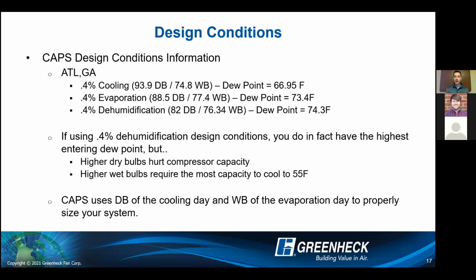So if you go into CAPS or you're working with Holden and they're in CAPS, the design conditions and the weather bin data that we're pulling out to standardize your selections are that dry bulb of the cooling and the wet bulb of the evaporation to make sure that we're hitting on, okay, this higher dry bulb is going to hurt compressor capacity, but we need to know about the higher wet bulb because that's going to require more capacity. Versus the dehumidification, while it does have the highest dew point, it might actually give you less capacity than you actually need for those other conditions.